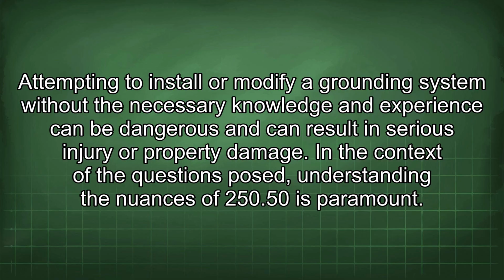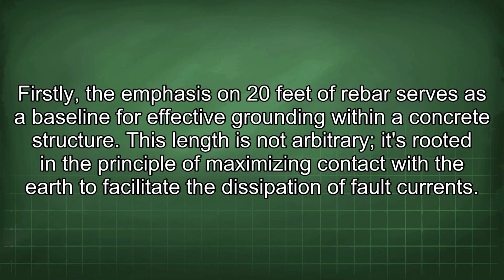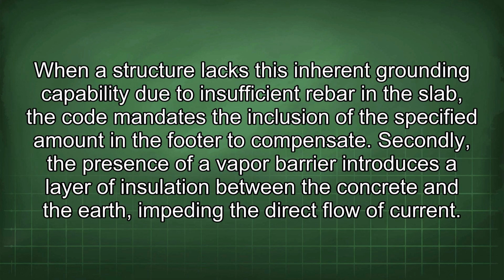In the context of the questions posed, understanding the nuances of 250.50 is paramount. Firstly, the emphasis on 20 feet of rebar serves as a baseline for effective grounding within a concrete structure. This length is not arbitrary. It's rooted in the principle of maximizing contact with the earth to facilitate the dissipation of fault currents. When a structure lacks this inherent grounding capability due to insufficient rebar in the slab, the code mandates the inclusion of the specified amount in the footer to compensate.